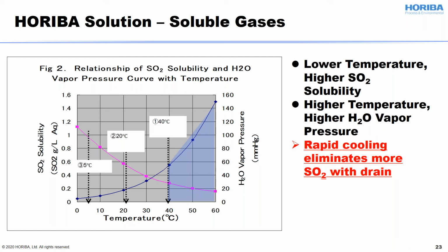There are three steps to cool the water, at 40 degrees C, 20 degrees C, and 5 degrees C. When you cool the gas at 40 degrees C, you expect the majority of water to come out, which is more than 50%. And at this temperature, SO2 solubility is still low. In the second step, the system cools the sample gas at 20 degrees C, and the amount of water is much less compared with that at 40 degrees C. Even though SO2 solubility is a little bit higher, the amount of water is less, which means you don't lose much SO2. Lastly, the cooler is set at 5 degrees C, and the system drops the rest of the moisture out.